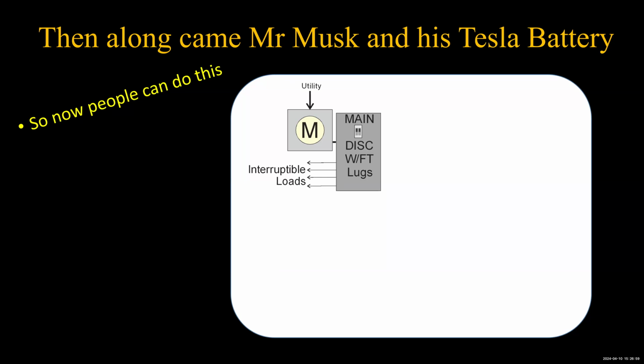Unless, of course, you decide to wire it differently and have a whole house backup—that's another story. But this is how it first started out, as a partial backup. You put this automatic relay in because the last thing you want is if the utility is down and you turn on some kind of other generation, you want it disconnected from the utility. If that generation feeds the utility when some poor utility worker is trying to rewire a down distribution line, they could get a surprise shock from somebody's PV system down the street, and that is not appreciated.